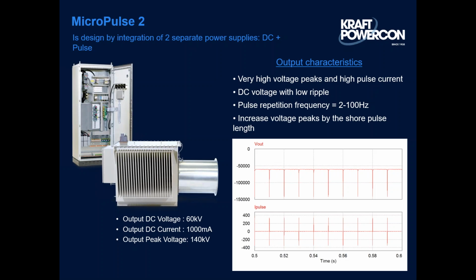We also have a micropulse, a new product that became commercially available this last summer. We have some large commercial installations and will be testing this product. Everyone has seen benefits of intermittent energization with the single phase TRs and also the SMPSs and the 3-phase TRs. This takes that concept to the next level - it gives a very quick pulse of very high voltage, building a very strong electrical field which migrates the particulates to the plate without all the counter effects of current going through the ash layer on the plate. Especially with high resistivity cases or aggressive electrodes with buildup on the plates, this provides very high efficiency at very low current and very low input power.